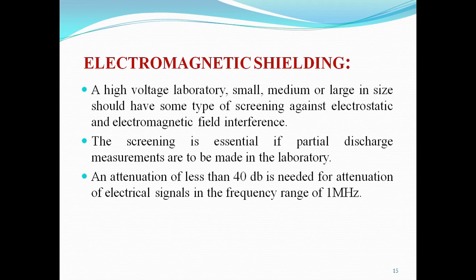Electromagnetic shielding. A high voltage laboratory, small, medium or large size, should have some type of screening against electrostatic and electromagnetic field interference. The screening is essential if partial discharge measurements are to be made in the laboratory. This is a very sensitive test in the high voltage laboratory. Therefore, a Faraday cage is required, and attenuation of not less than 40 dB is needed for electrical signals in the frequency range of 1 megahertz. So we will find this kind of arrangement in the partial discharge laboratory. Complete screening is there in the partial discharge laboratory.